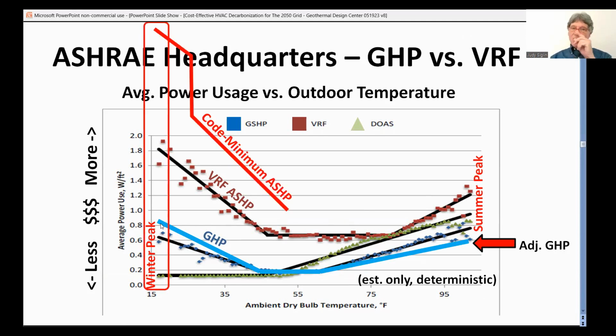So let's overlay what a basic air source heat pump runs as. That thing is much less efficient than the VRF. And the big deal is that when it gets really cold, down to maybe below 45 degrees or so, these things will cut into electric strip heat. And that is a much more expensive thing to run, what they call coefficient of performance, just electric strip.